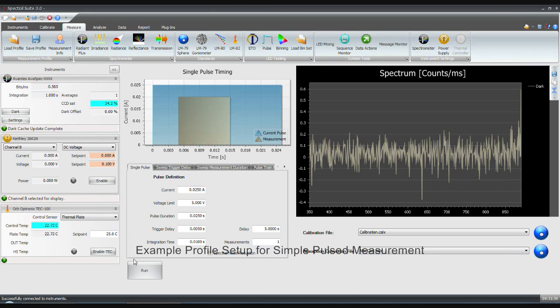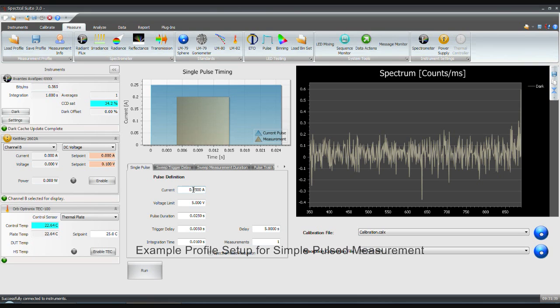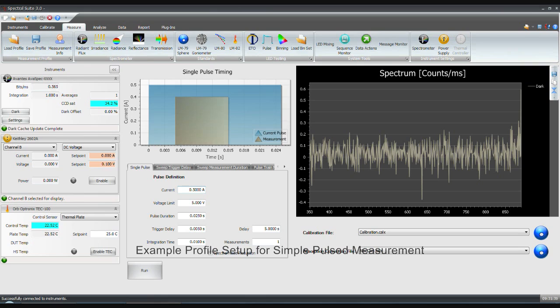Set the current setpoint, compliance voltage, pulse duration, integration time, and trigger delay. The trigger delay field will only appear if supported by the power supply. The graphic will update to reflect the current settings.